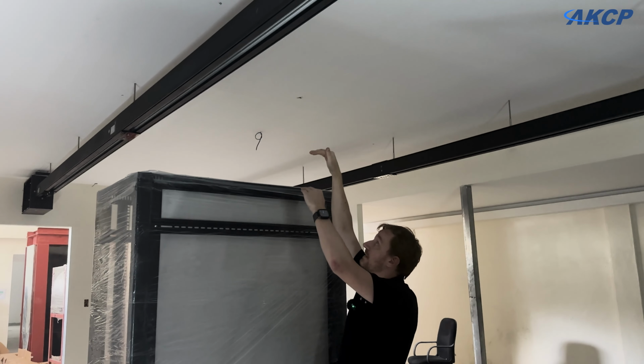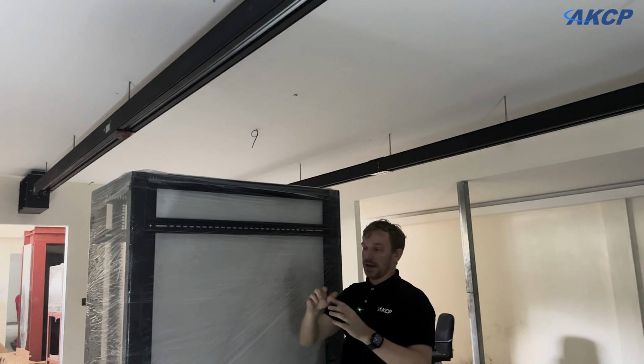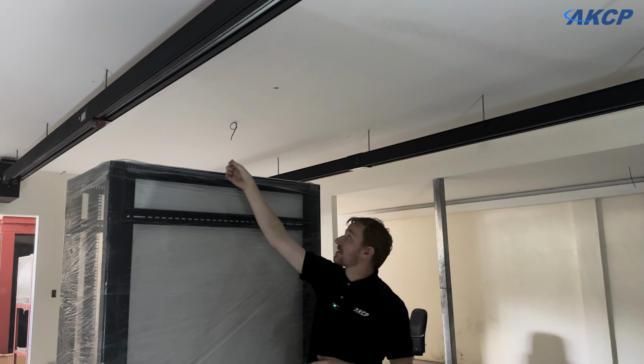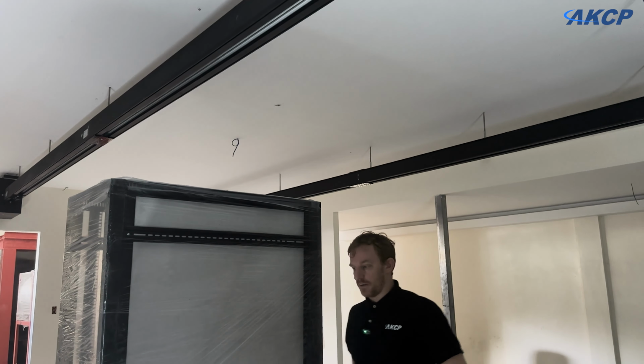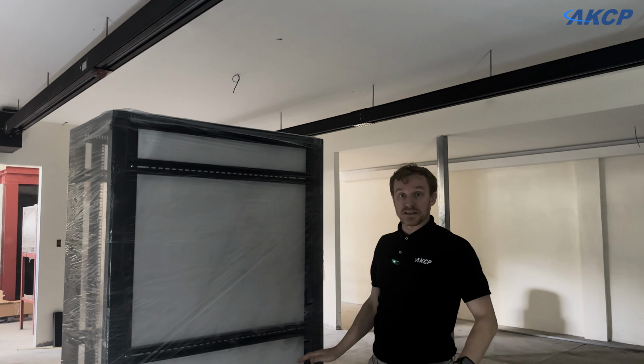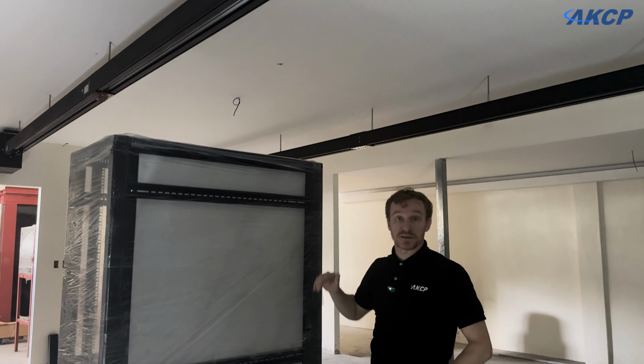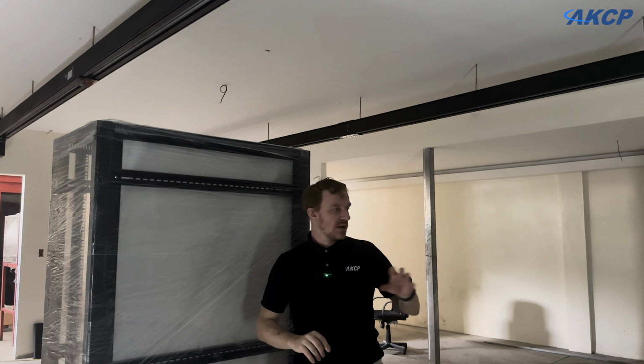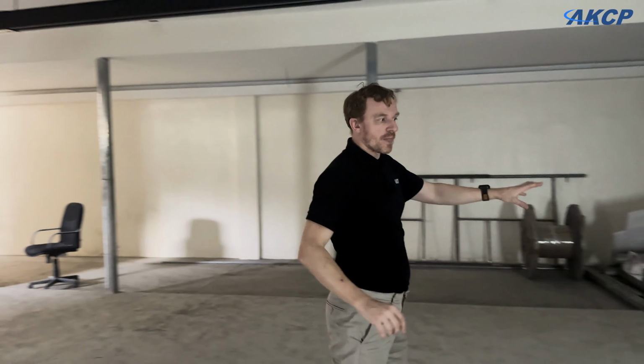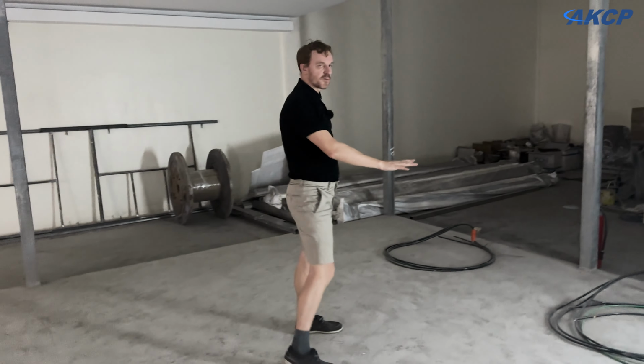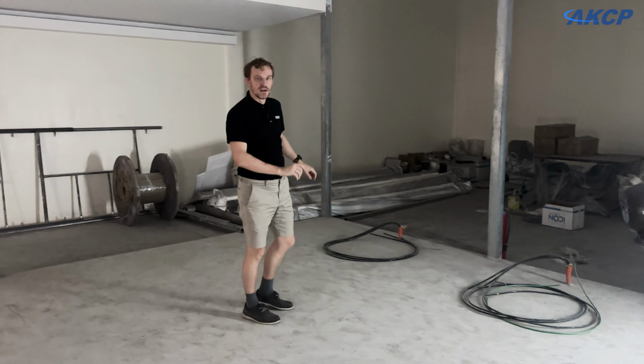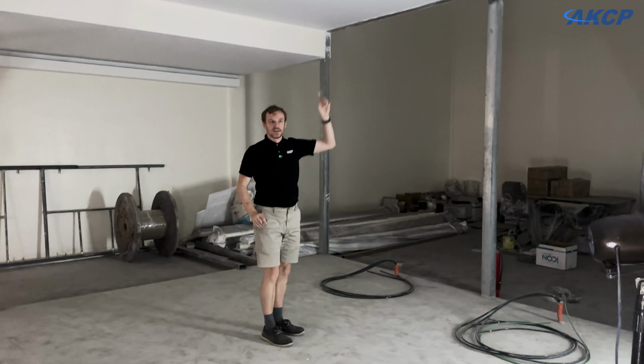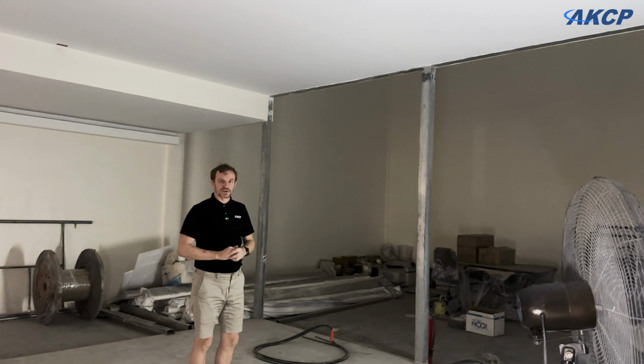In hall number 2, we have cold aisle containment, and we don't have the high ceiling, so we're showing here 2 different types of data center setup. You can see the clearance between the top of the rack and the bus duct is quite tight. We have the distribution box there, with just enough space to plug it in, so we couldn't have a raised access floor here with the overhead bus ducts because of the ceiling height.